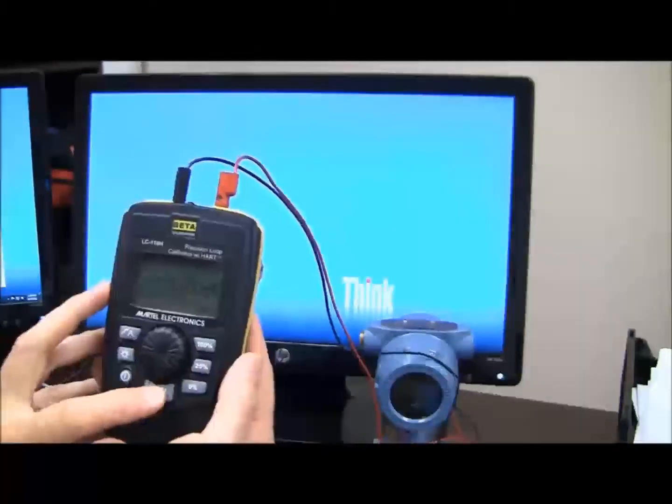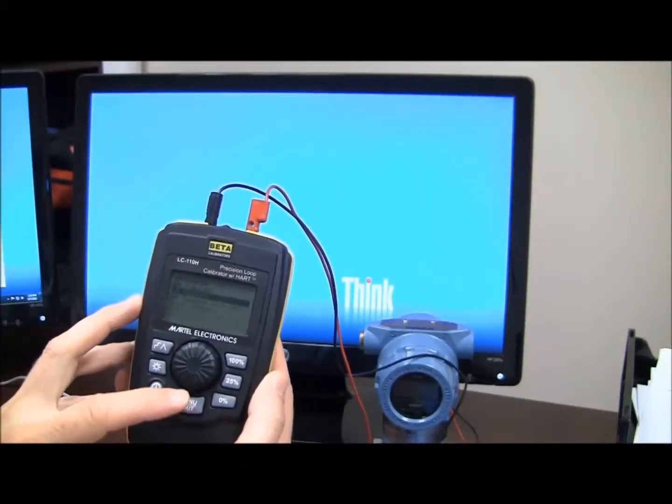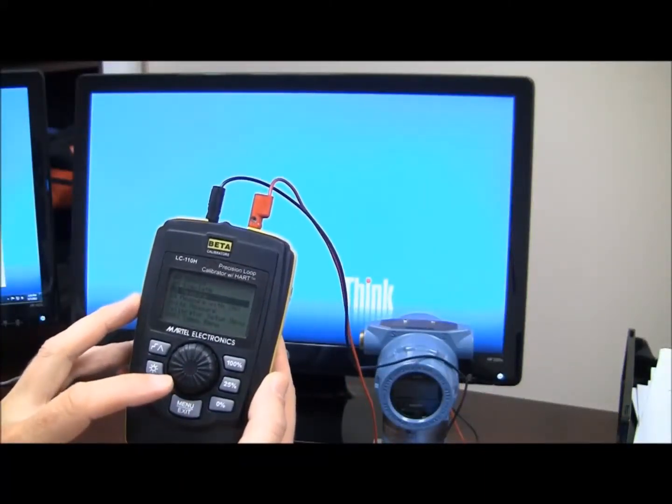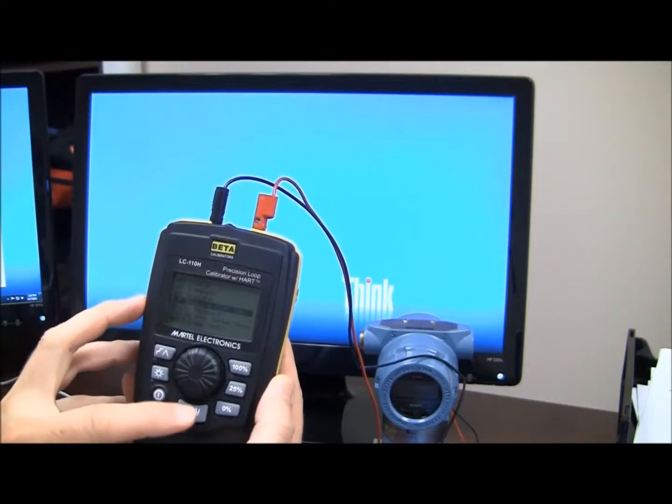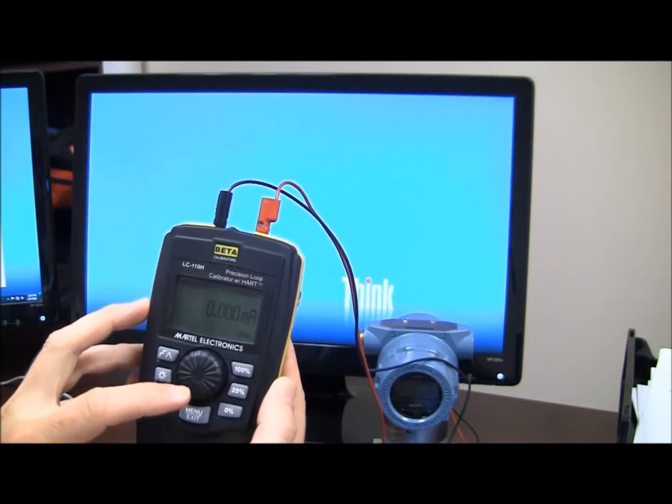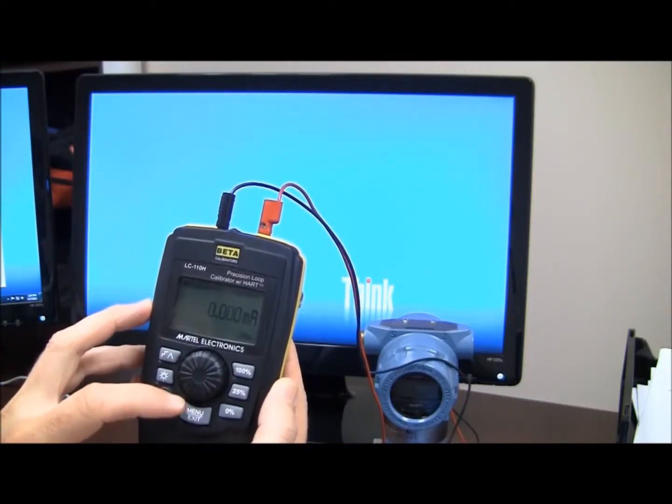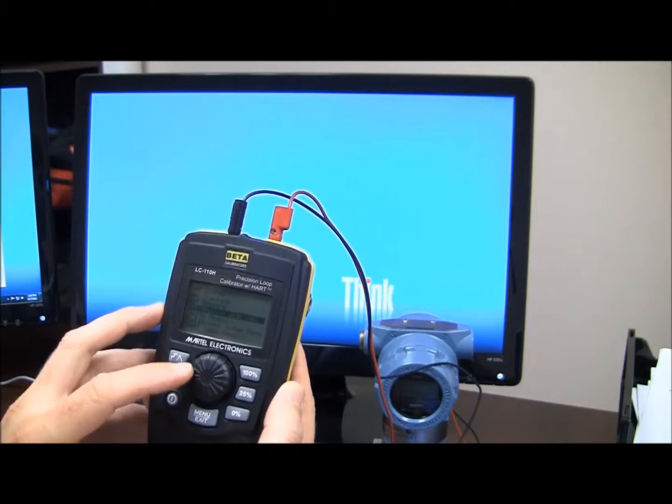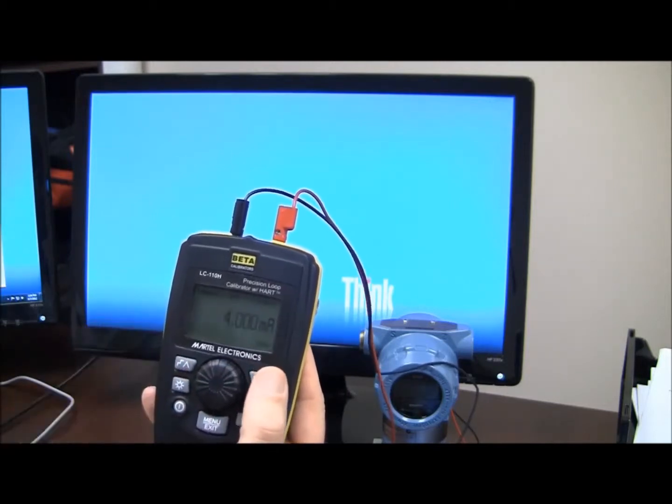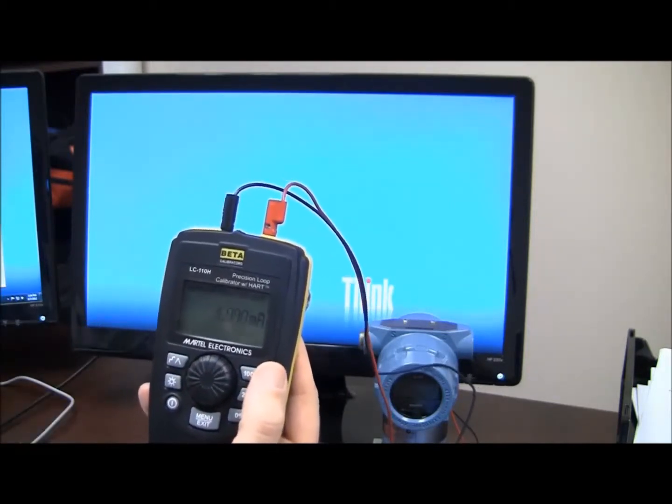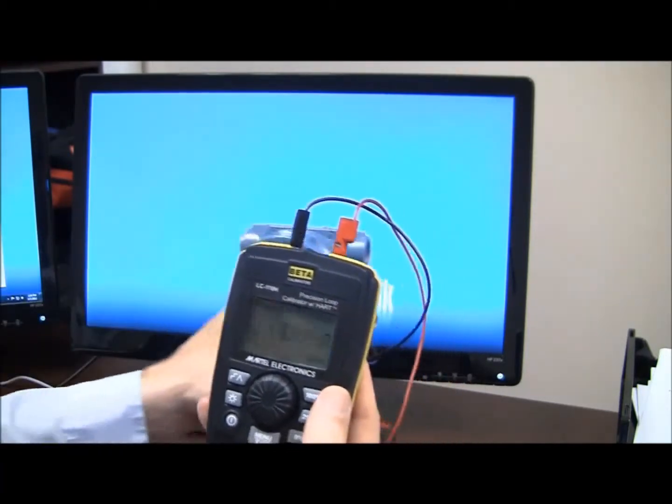I'm going to go in the menu, and we're going to go to milliamp measure with 24 volts. We're going to select that. As you see here, I'm reading 4 milliamps, transmitter's powered up.